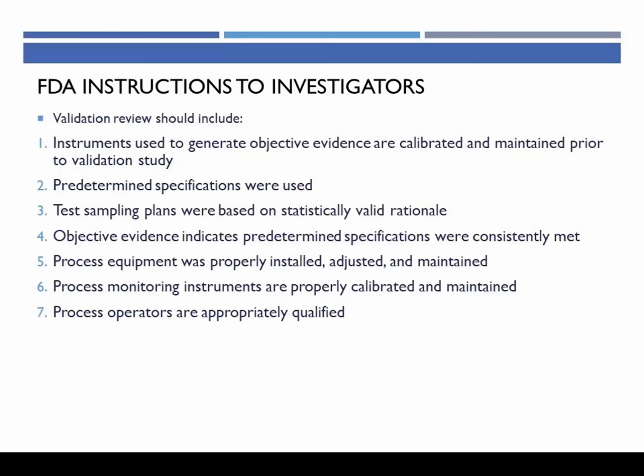They're going to look for objective evidence that indicates the predetermined specifications were consistently met. They want to see that process equipment was properly installed, adjusted, and maintained. They want to see that any monitoring instruments were properly calibrated and maintained. So expect them to ask for those records. Frequently, we'll see the FDA investigator go out to the shop floor and write down some equipment numbers, some gauge numbers, and then say, I want to see the records for calibration and maintenance on this.